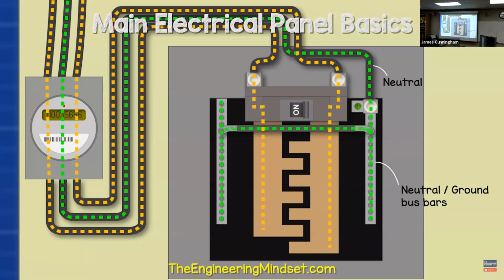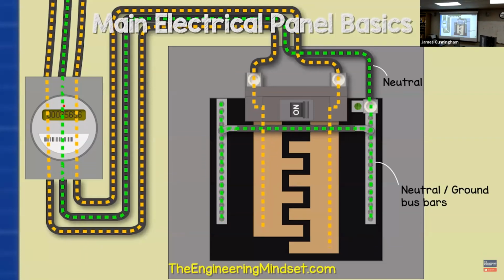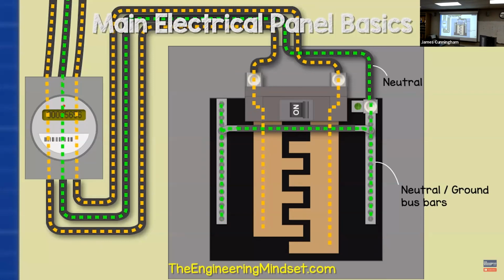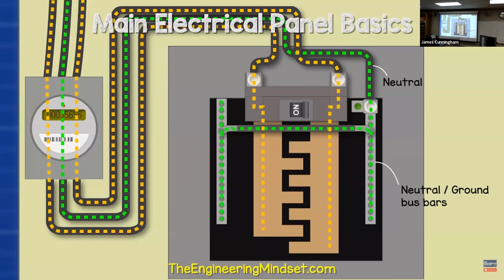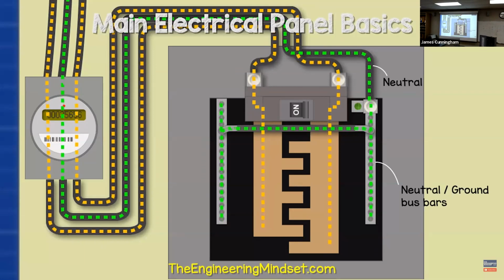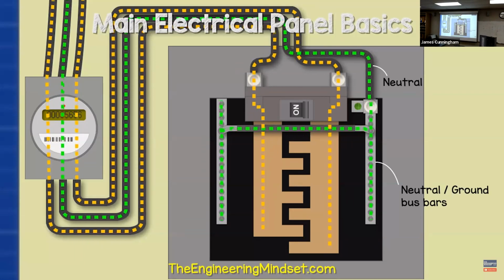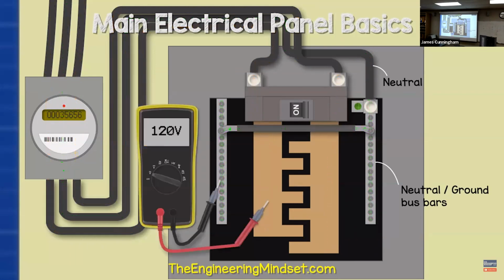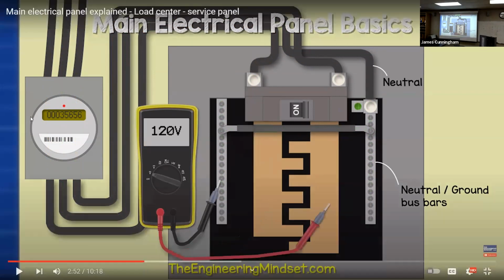So the two hot wires will provide electricity, and once it is used, it will return to the transformer via the neutral bar. It is still AC alternating current, but to make it easy to visualize, I've only animated the current flowing in one direction, so you can see the path it will take. Now, if we were to take a multimeter and connect one lead to the bus bar and the other lead to the neutral bar, we would get a reading of around 120 volts. If we connect the multimeter leads to...